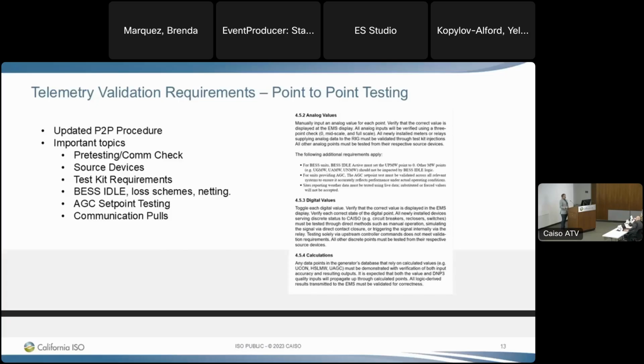And then for our communication pulls, we go into greater detail about why it's important to actually disconnect the source device at the source. Sometimes we get questions like, oh, well, why can't we just disable a port and simulate this? And it's really important to actually disconnect it at the source. For example, like a MET station, where maybe that MET station is communicating to a data aggregator over Modbus. We want to make sure that that logic is in place to communicate the quality changes into DNP3 protocol from Modbus, so that we're actually getting the correct visibility on that.